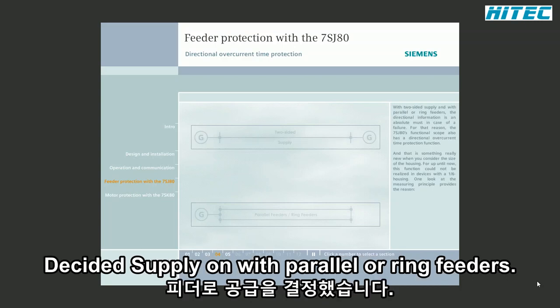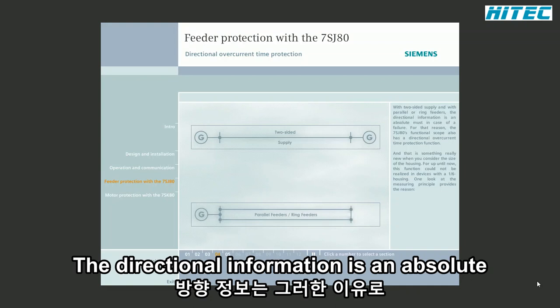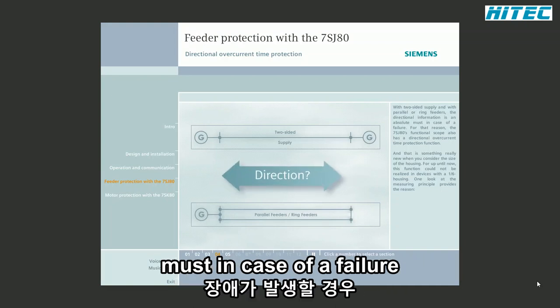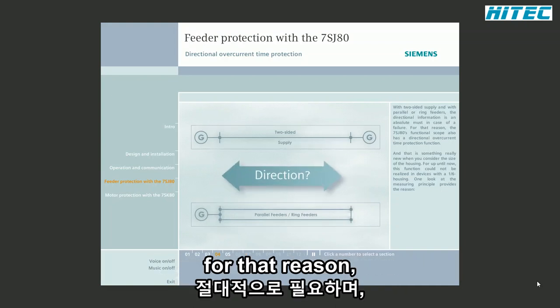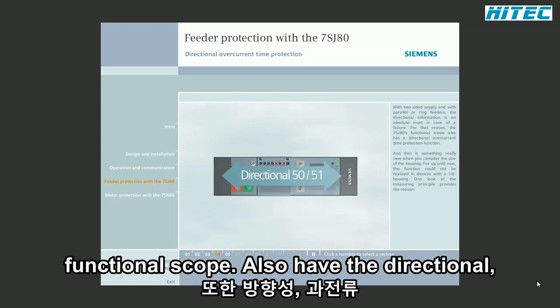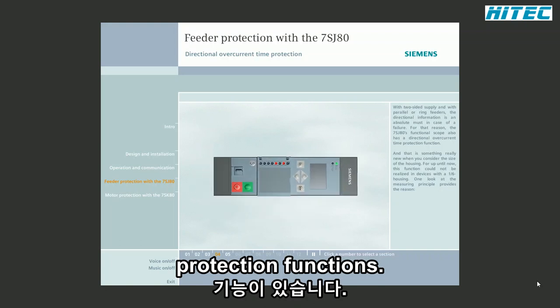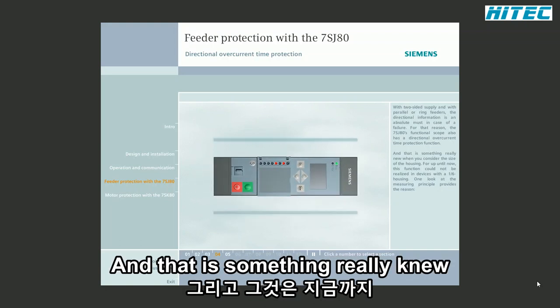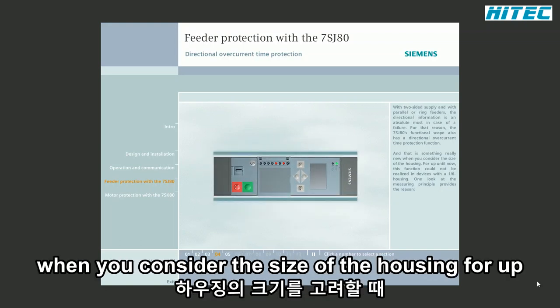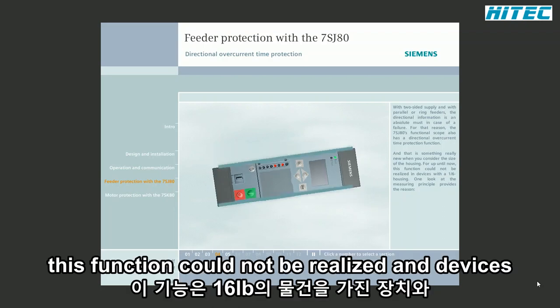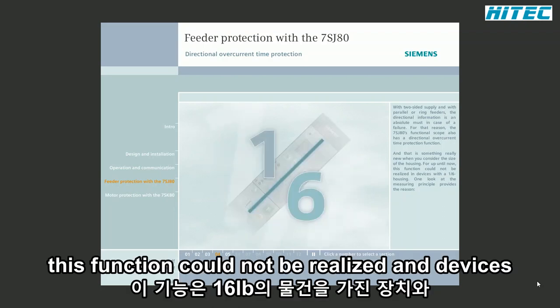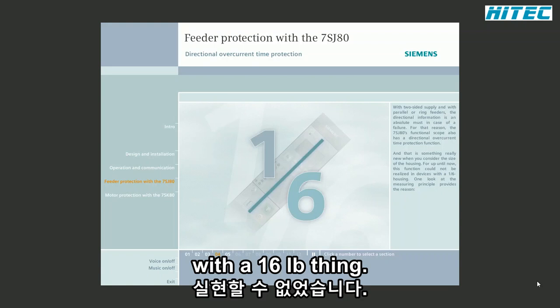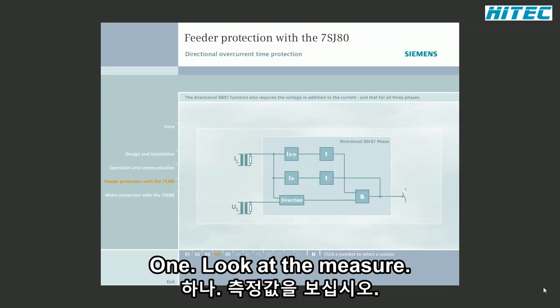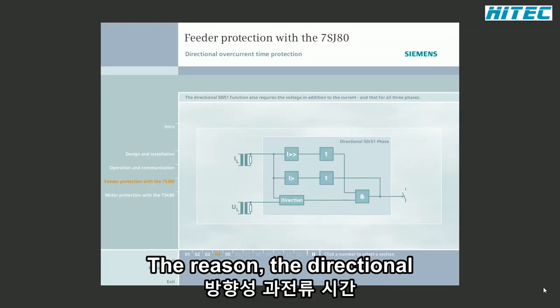With two-sided supply and with parallel or ring feeders, the directional information is an absolute must in case of a failure. For that reason, the 7SJ80's functional scope also has a directional overcurrent time protection function. And that is something really new when you consider the size of the housing. For up until now, this function could not be realized in devices with a 1/6 housing. One look at the measuring principle provides the reason.